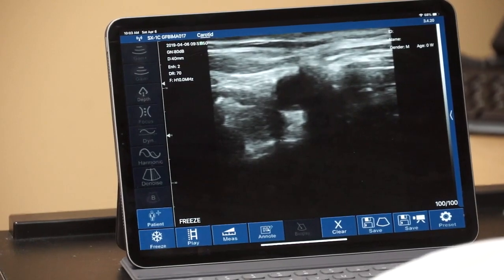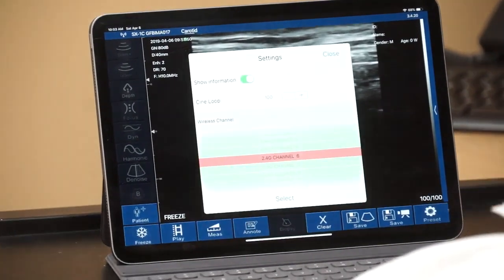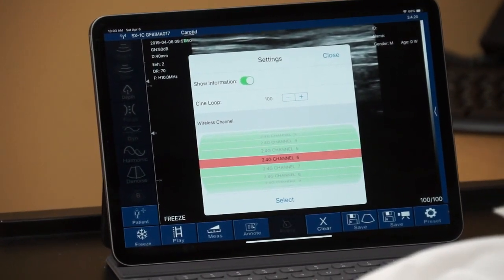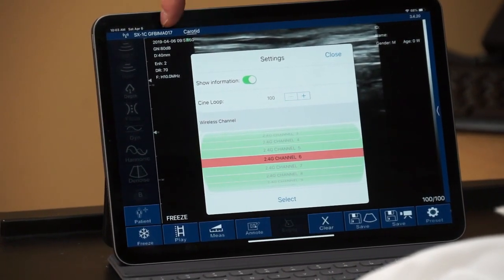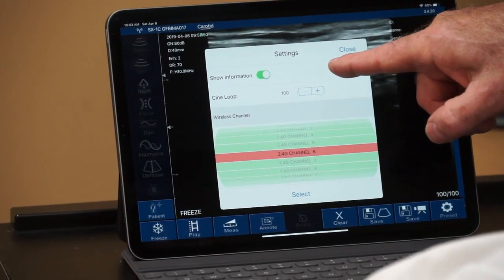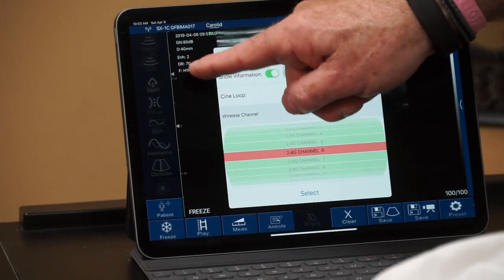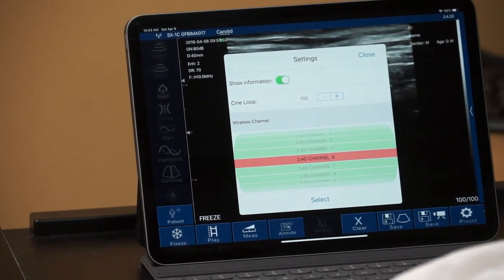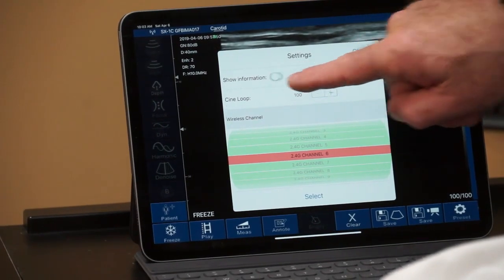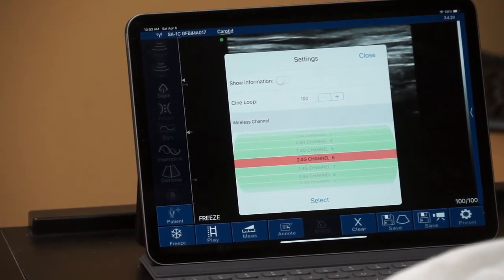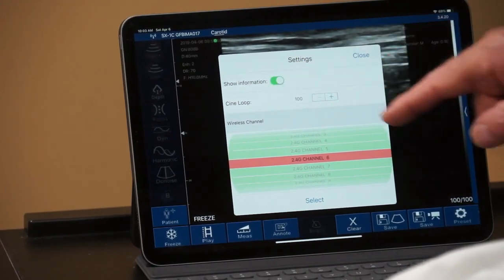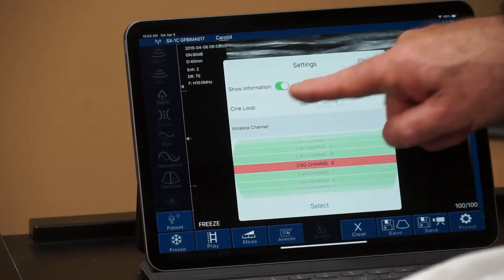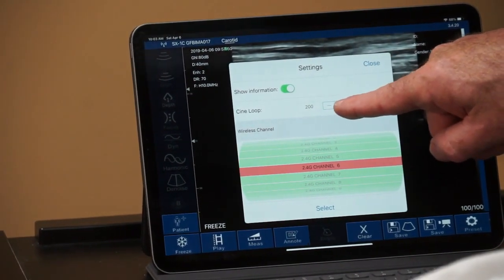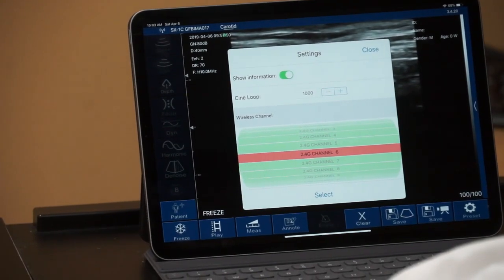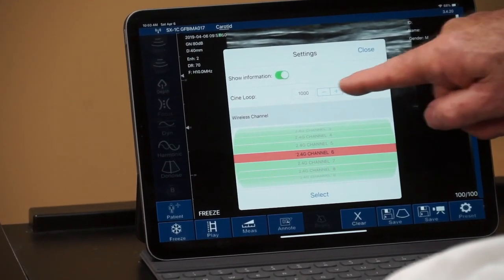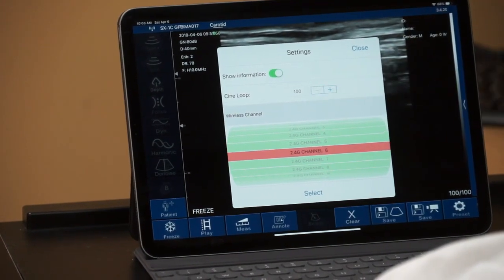The very last function to demonstrate is the preset button. Ordinarily, we think of presets as the examination presets for the parameters, but in this case, it's a small screen that gives us three other options. If for any reason the white lettering, patient ID, or parameters were problematic in the viewing screen, if we toggle that show information off, the white lettering disappears from the screen. Toggle it back on and the parameters and patient information reappears. Cine loop is simply a way to go up from 100 frames. This will go all the way up to 1,000 frames, which is approximately a 100-second video. Approximately 10 frames per second. We keep it down for demonstration purposes.